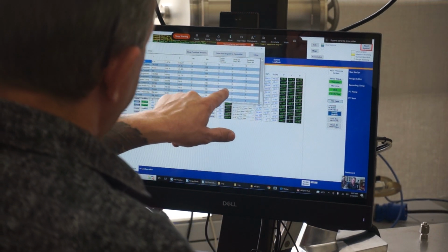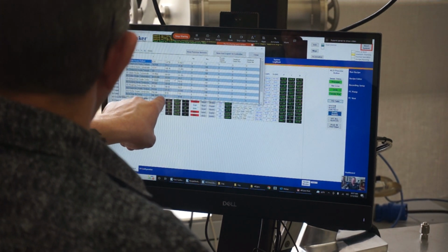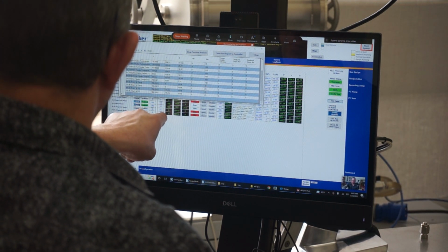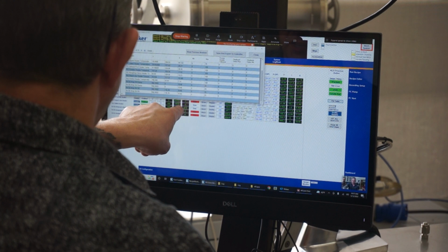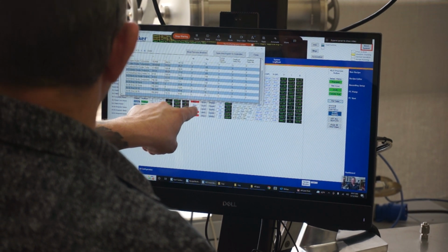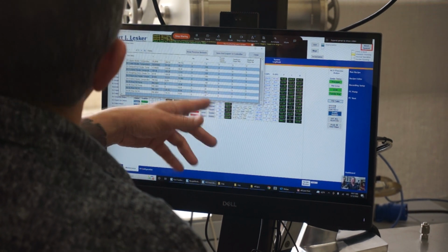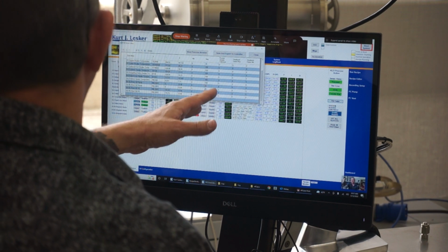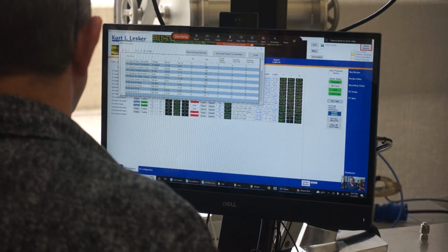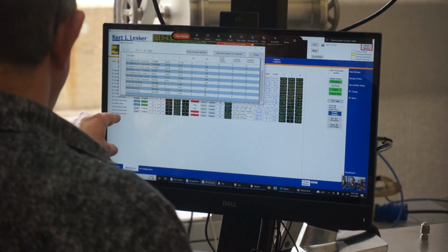Also in this PID table, you could limit the output, so you could set the max output of the heater. You can limit to 20, this is in percent. You can limit to 25% output on your ampule heaters.